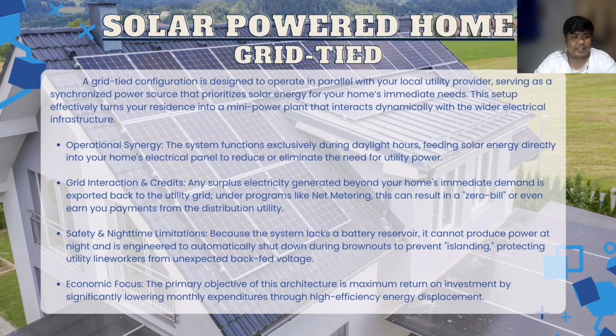Next is safety and nighttime limitations. We must be clear about the nighttime limitation and the safety protocols, because this architecture lacks a battery reservoir and cannot produce or provide power at nighttime. More importantly, the system is engineered with a critical safety feature: it automatically shuts down during a brownout. This is a mandatory requirement to prevent what we call islanding. If the utility grid is down for repair, it is vital that your solar system doesn't backfeed voltage into those lines. This protects utility line workers from unexpected high voltage while they are trying to restore service. While it means you are without power during a blackout, it ensures your system is a safe and responsible part of the national grid.